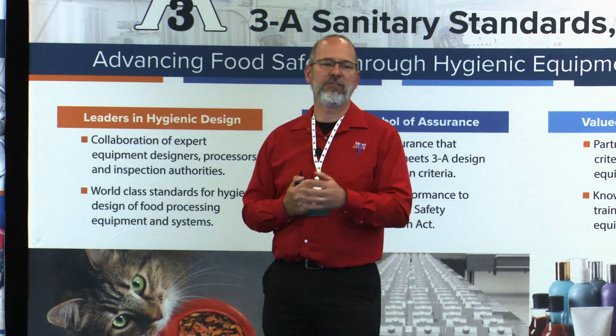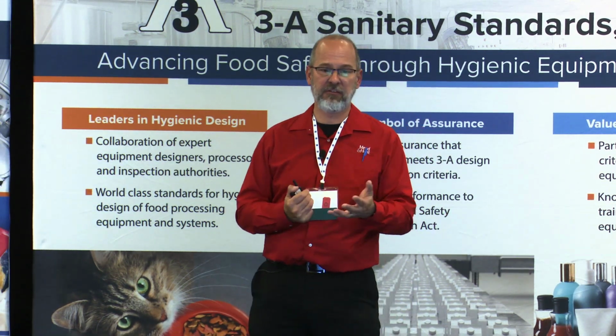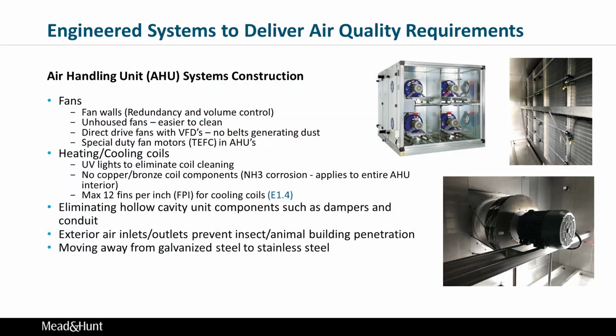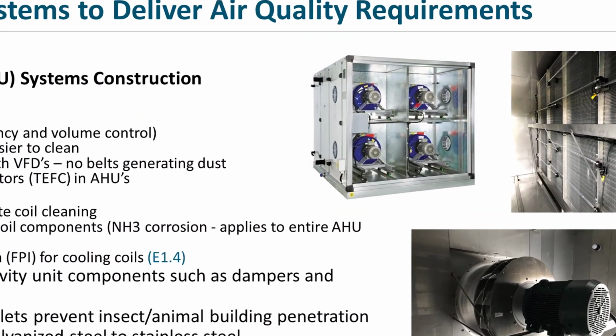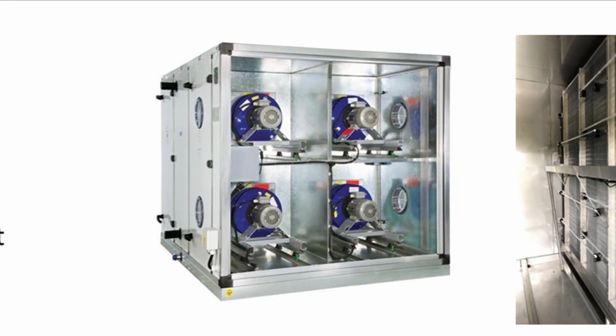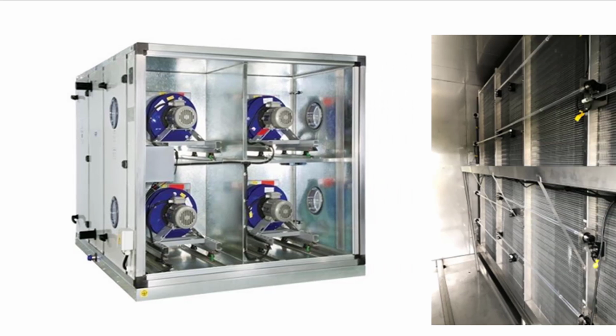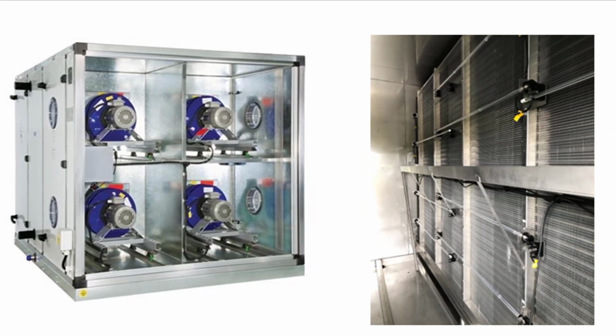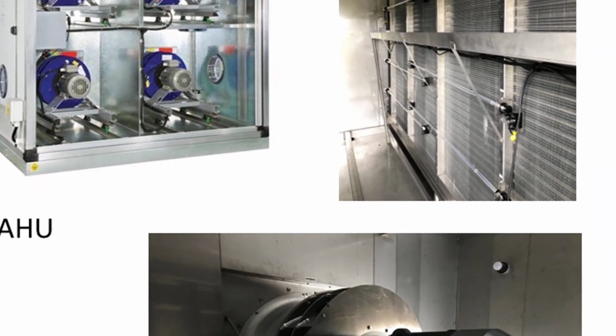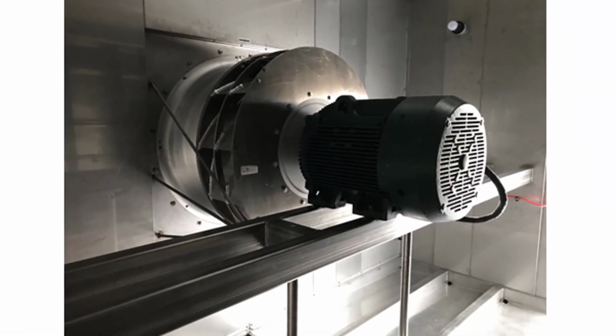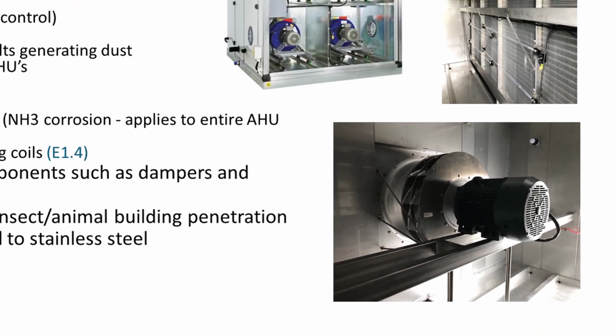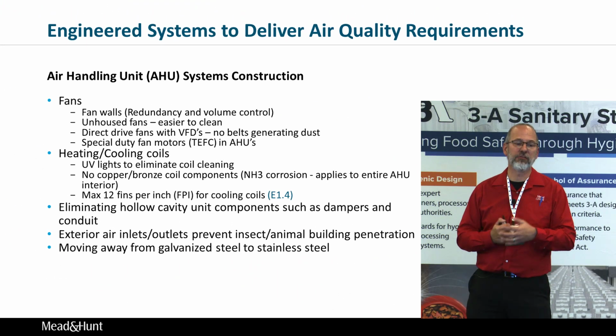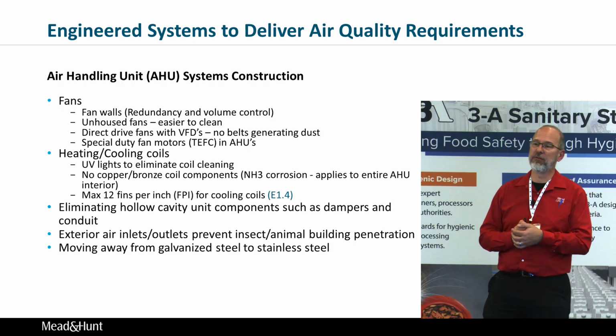Some of the other components in an air handler, fan systems. We're starting to see more and more fan walls, like that image with the box there. Instead of having one big fan, you'll have an array of fans, so if a fan fails, you can keep limping along on the other ones you have and not have to shut down production. So some little redundancy there. Don't put fans in with fan belts. Make them direct drive and put them on a VFD. It's easy to balance, and now you won't have fan dust or belt dust being generated inside your air handler. And also put in special duty fan motors that can be washed down.